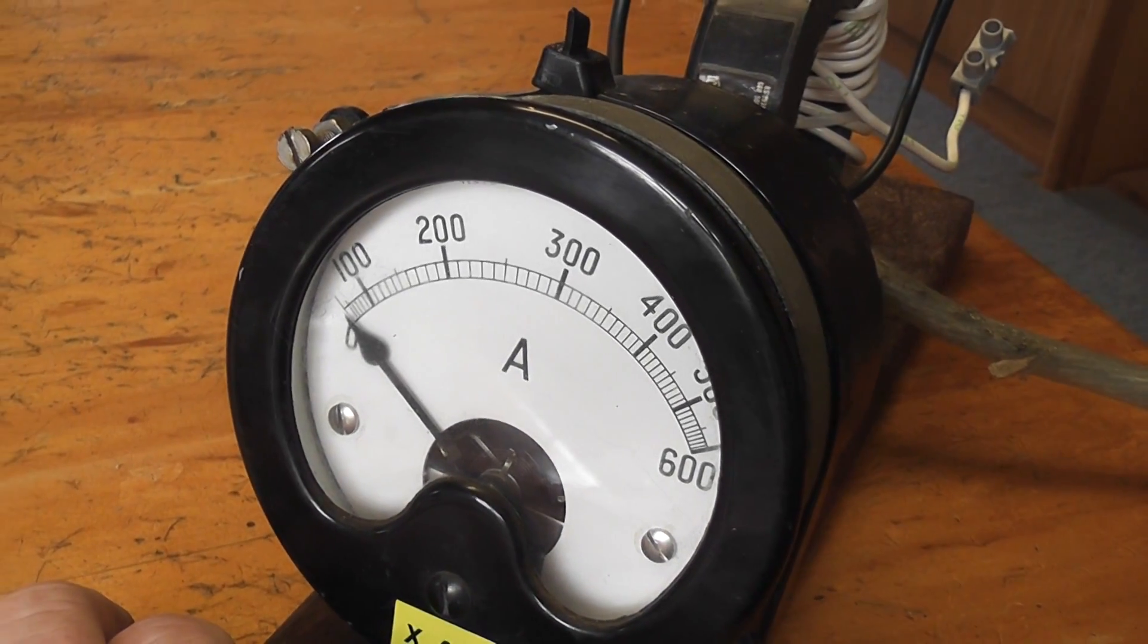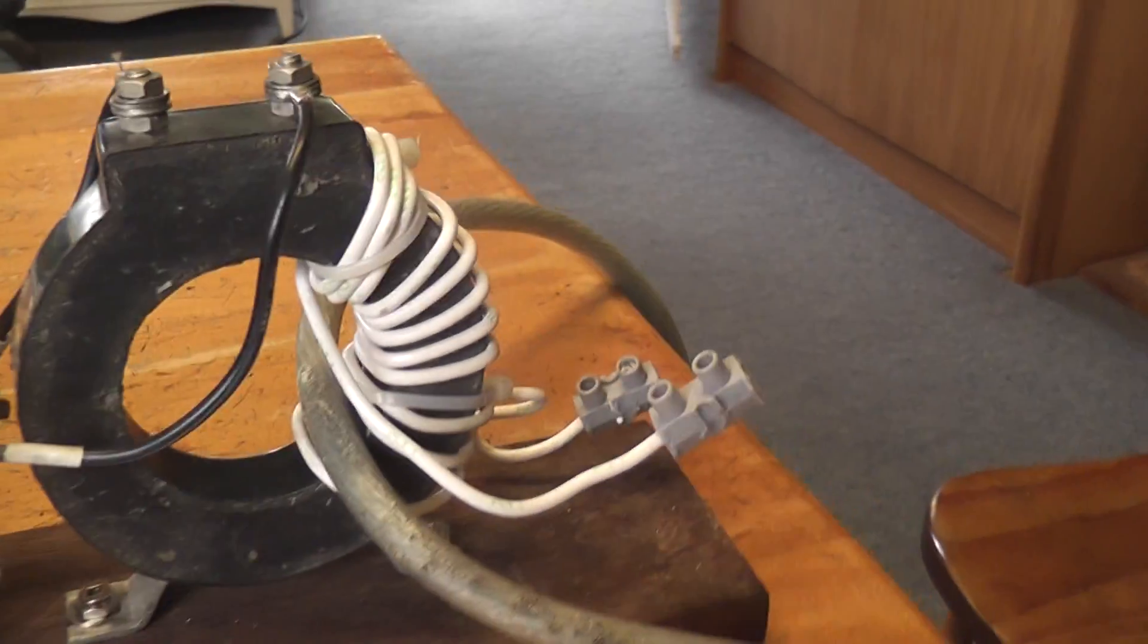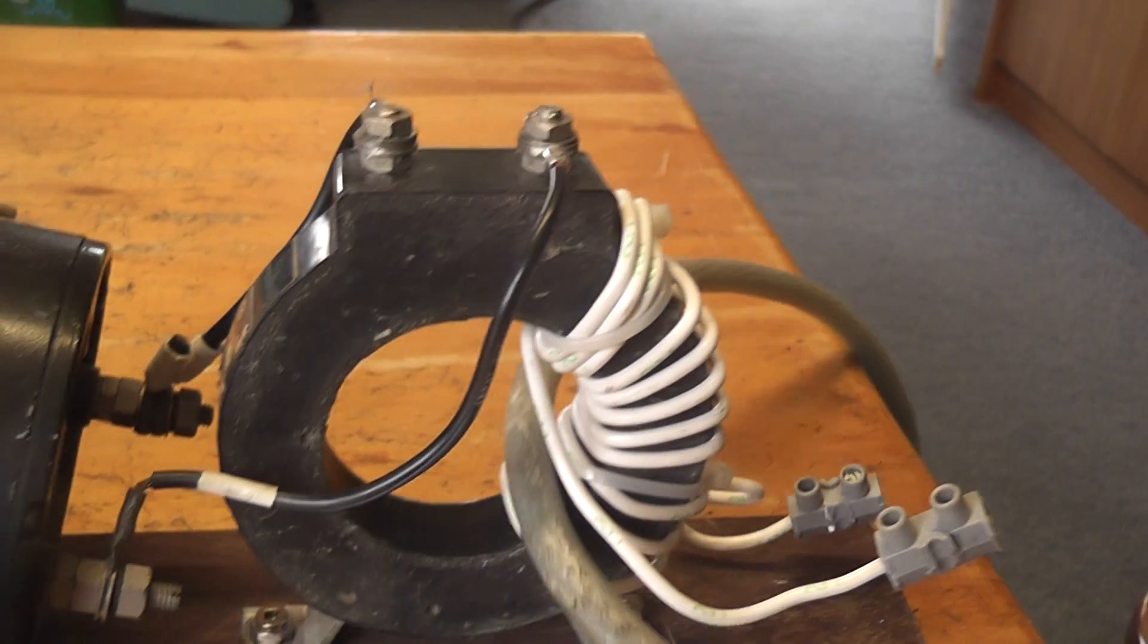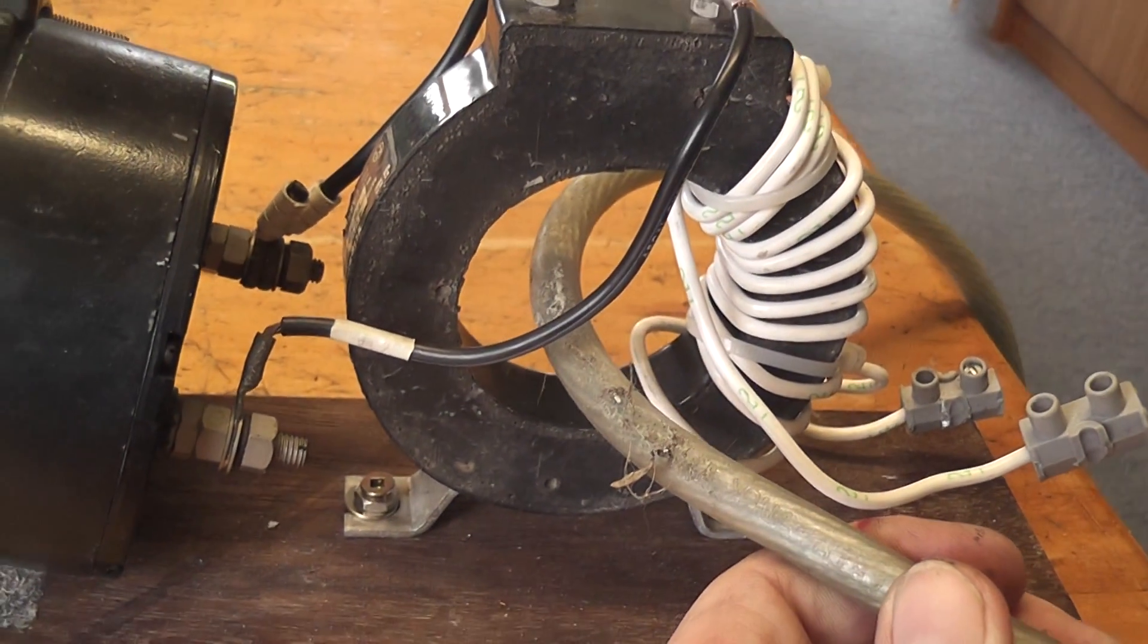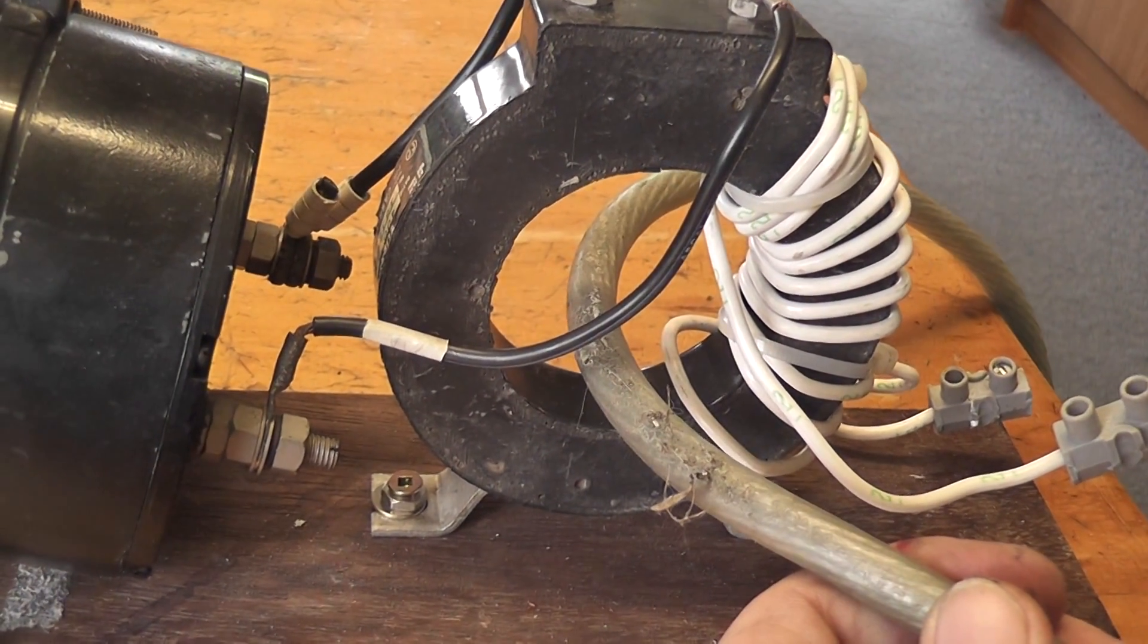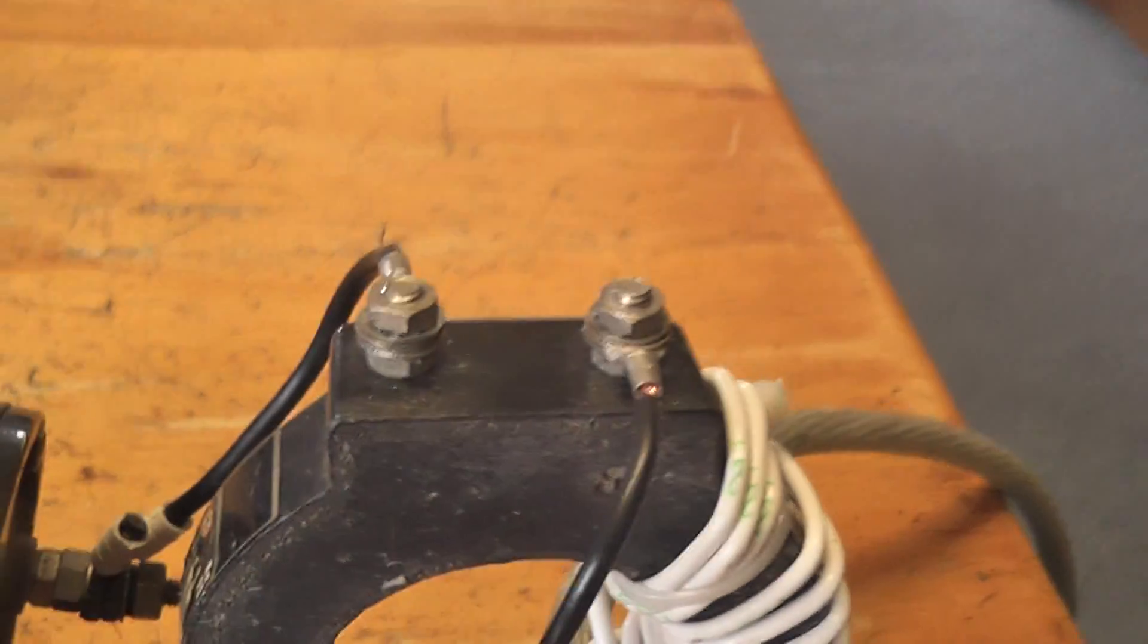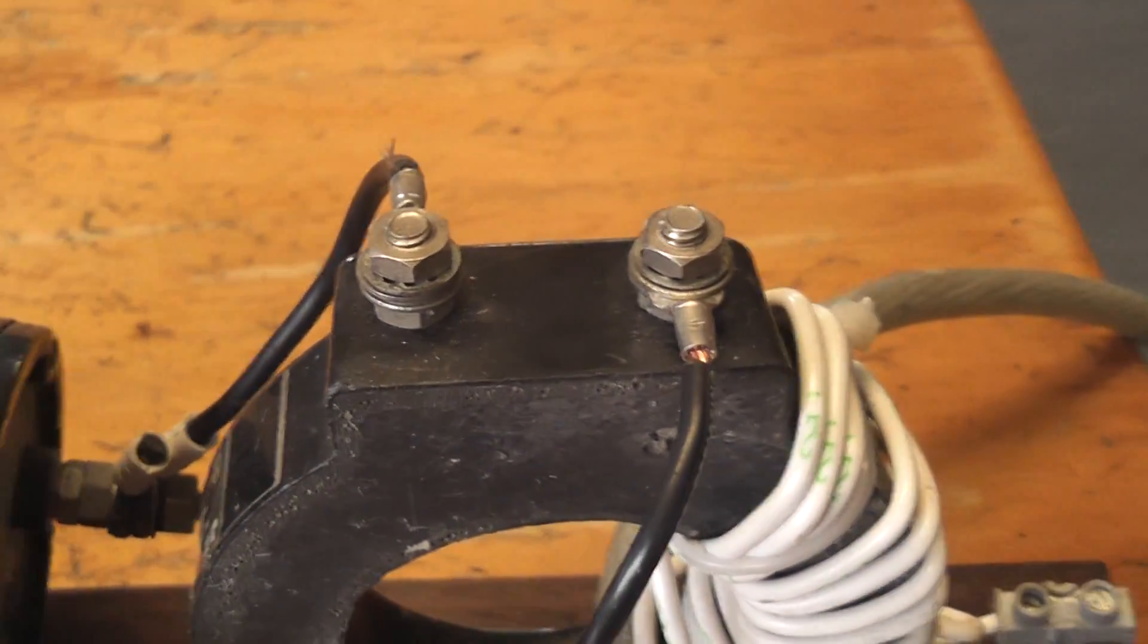The meter can still be used for 400 ampere as well by basically putting one turn of thick gauge cable through there. Use that as your primary and then the secondary output is from the CT terminals which goes straight into the ammeter itself.